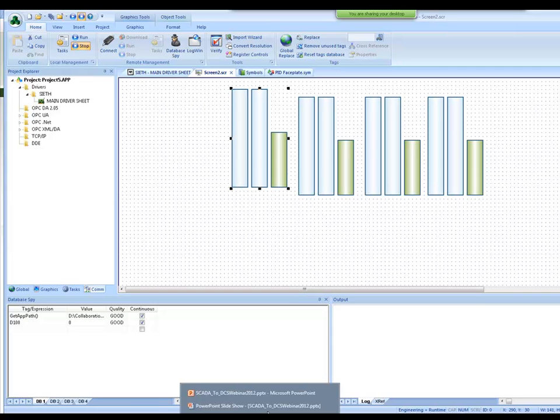with multiple InduSoft thick clients hitting on them with the CRISP driver. And there's a lot going on in the DCSs, and the active one is typically running at 9 to 10% utilization, which is good. We want all of those processes to operate freely and not be hindered by a really busy CPU.